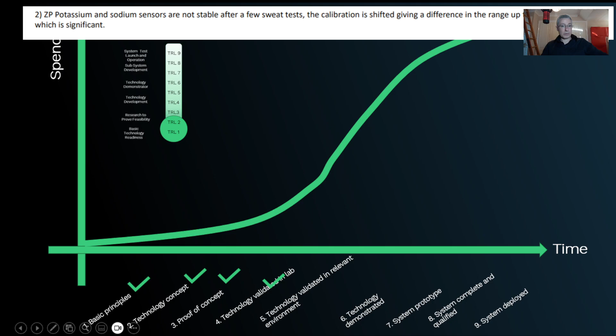One of your concerns is about resolution. I think you can already resolve plus or minus 0.5 millimolar. The reason you think you can't is because you test by pipetting on and pipetting off, and every time you pipette on and pipette off, you have a signal plus or minus an offset variable, and that offset variable is what's clouding your resolution and also concerning you on accuracy.